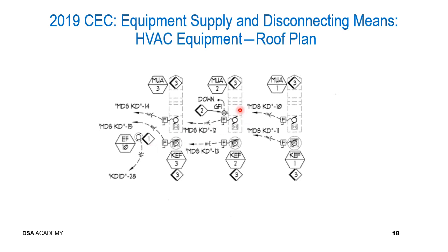Another important thing to see and to understand is, since this is rooftop mounted equipment, this equipment is going to require service and repair at some point in its life, and because of that, an outlet needs to be provided for the service personnel so that they can run their power equipment to use in the repair and servicing that they're going to perform. As you can see here with this note number 2 in a diamond pointing to this receptacle that's identified as GFI, standing for ground fault interrupter, this is the required receptacle that is required on the line side of this particular fused disconnect. Does that make sense? And this is what's going to allow the service personnel to shut the power off to this particular unit and still have power supplied for them to use at this outlet for performing their service of the equipment.